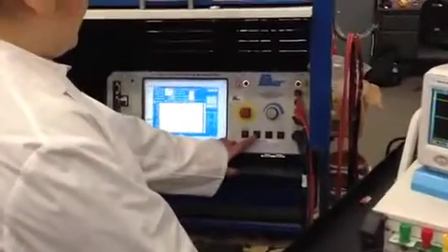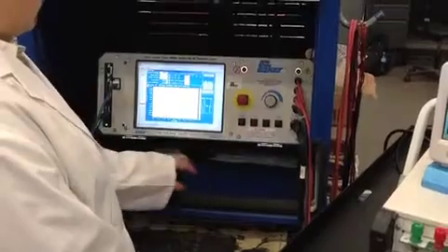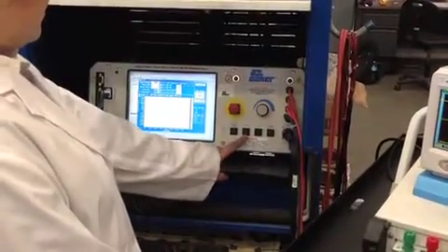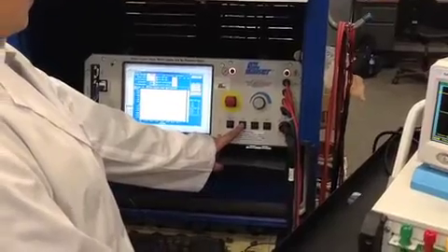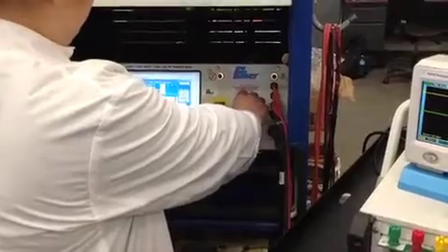In front of her she's pointing now at a Baker Surge Tester. This will apply the voltage to the motor and she'll be raising the voltage until we achieve the partial discharge.